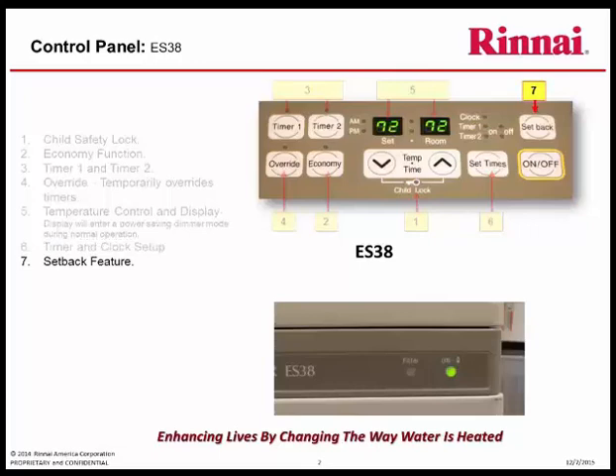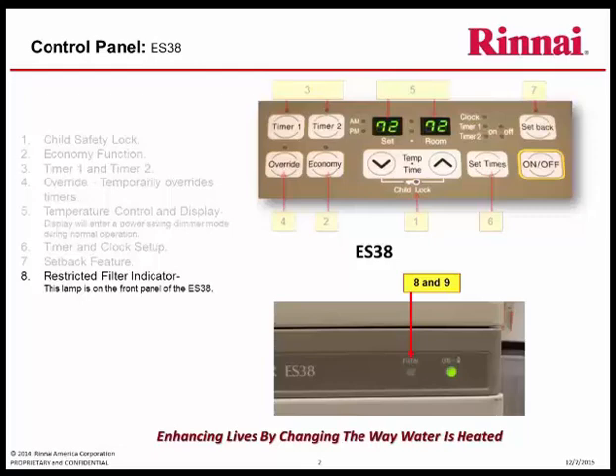Setback feature: this allows for energy savings when no one is present in the structure, or can be used as a frost protection feature. Restricted filter indicator, located on the front panel, lets you know that not enough air flow is passing through its cabinet, which is generally an indication that the air filter has become clogged.